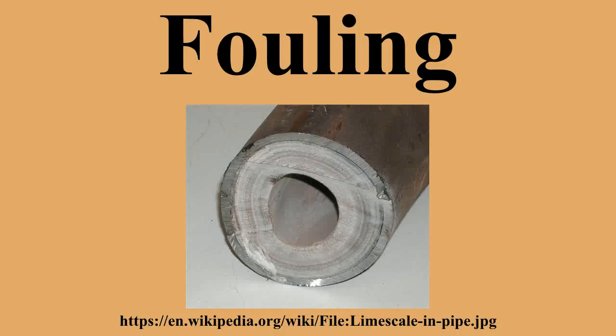Whereas chemical cleaning causes environmental problems through the handling, application, storage and disposal of chemicals, the mechanical cleaning by means of circulating cleaning balls or offline, bullet-type cleaning can be an environmentally friendlier alternative. In some heat transfer applications, mechanical mitigation with dynamic scraped surface heat exchangers is an option. Also, ultrasonic or abrasive cleaning methods are available for many specific applications.